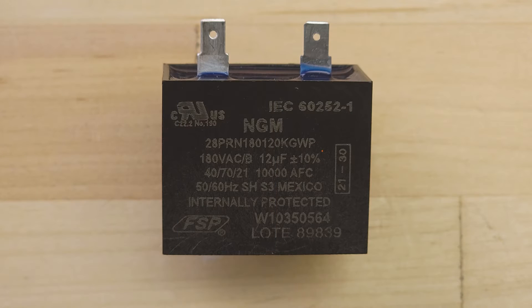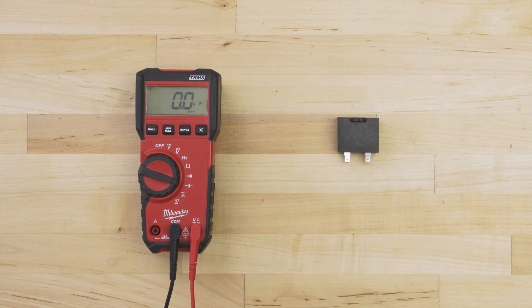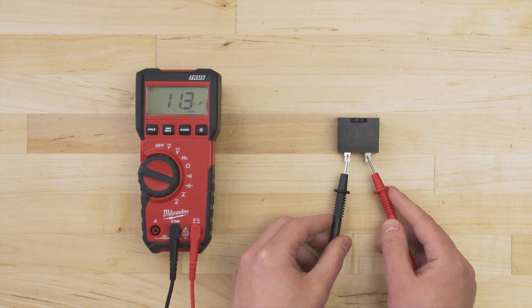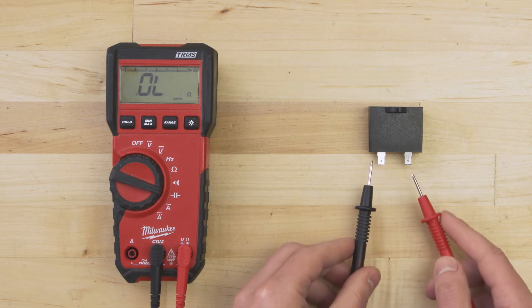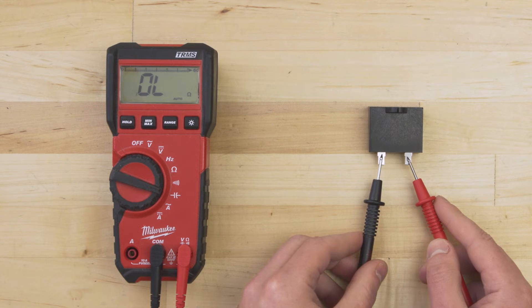On the side of the capacitor you'll see the capacitance rating in microfarads. This is what we'll be referencing. Set your multimeter to the capacitance setting. Now test between both terminals and wait 5 seconds. The reading should be within 10% of the rated value. If there is no reading and no continuity or the capacitance is outside of this range then the capacitor is faulty and should be replaced.